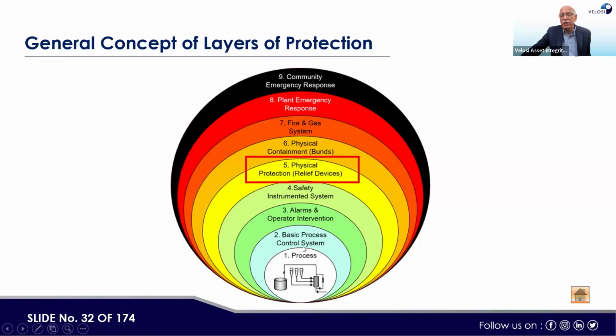Then there is the basic process control system, we call it BPCS, which is automated control of the plant operations. In the same BPCS there are alarms, and in response to critical or normal alarms, operators are required to intervene in the operational aspects, and they can remove the upset condition of the plant. Then, if both the basic process control system and the operator are unable to take corrective action, there are ESD systems. The ESD system can trip the plant if BPCS conditions are not being met or an alarm is not attended by the operator, and then the ESD system can automatically take control.